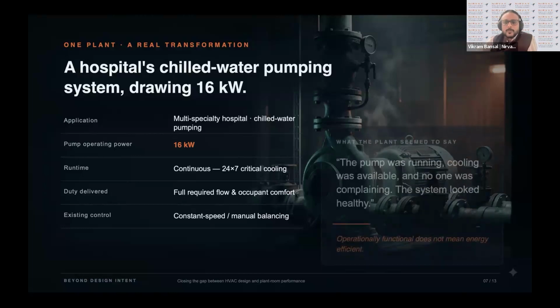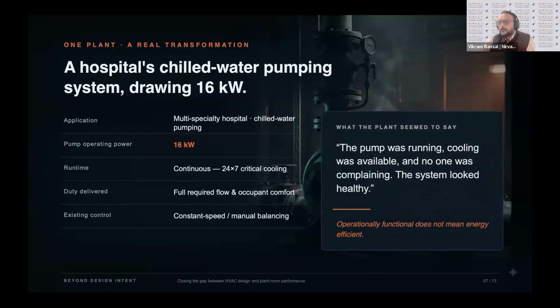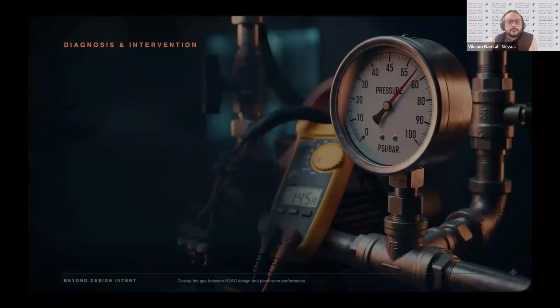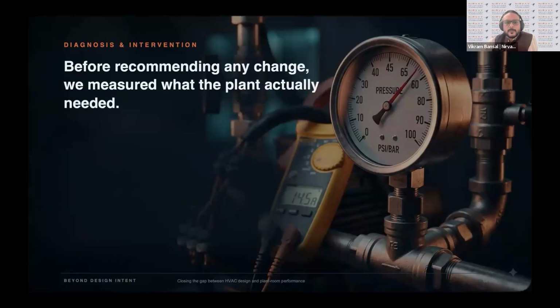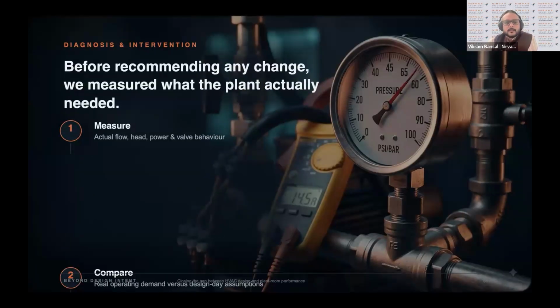So the pump was running, the cooling was available, but nobody was measuring how efficiently the system was running. When we went to the site and measured it, we didn't just change the logic straight away. We measured what was happening at the site, and what the behavior of the system was.